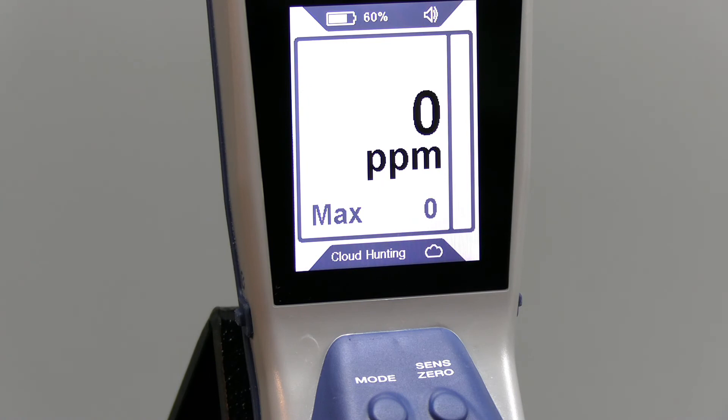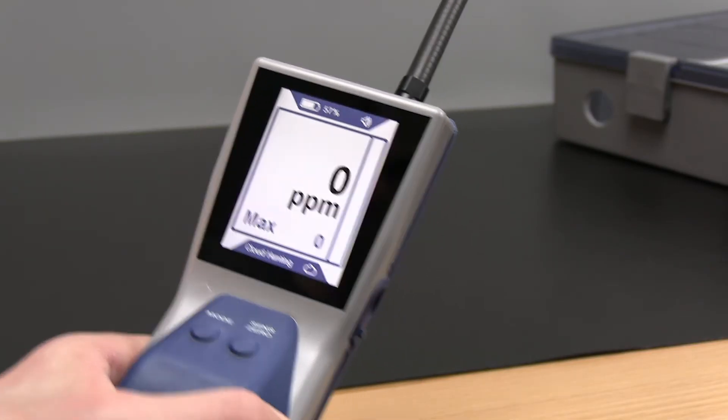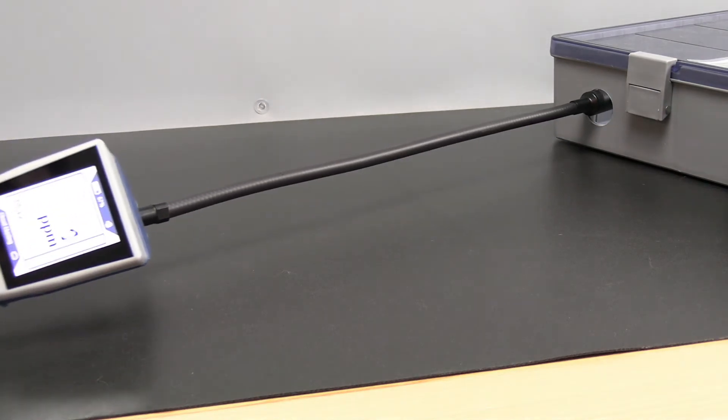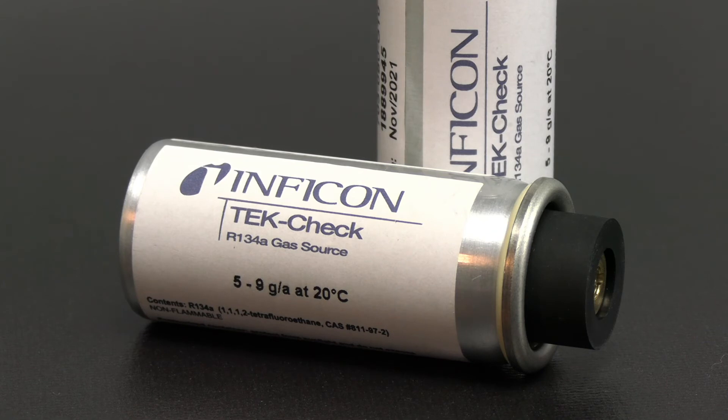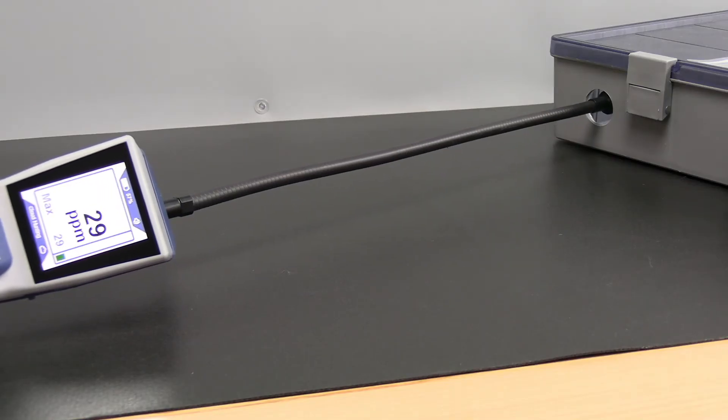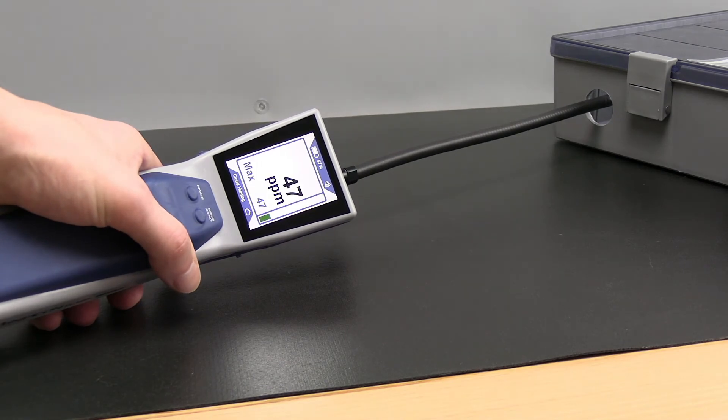Cloud Hunting Mode, exclusive to D-TEK Stratus, displays the refrigerant concentration in the air in parts per million. This allows you to read the display and follow the number to find areas of higher concentration, guiding you straight to the source of the leak. The higher the PPM, the closer you are to the leak.